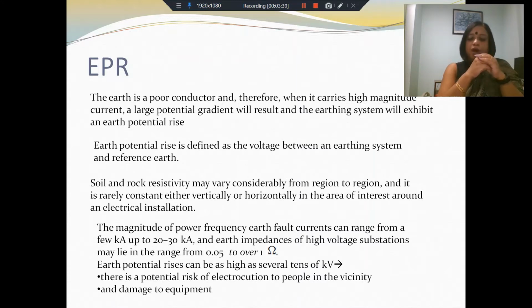But when you are talking about high fault currents or high lightning currents, the current magnitude can be extremely high. It can be in the range of a few 20 kiloamps or even more. In that situation, if you have a very high current I multiplied by even a small resistance R, the product I into R will be very high. So if you have two points in the earth with a resistance R between them, even if that value of R is small, a very high magnitude of current will result in a very high IR and a very high potential difference between those two points.